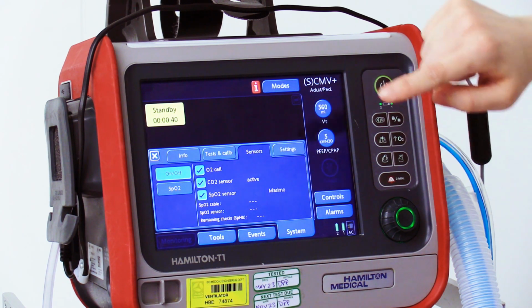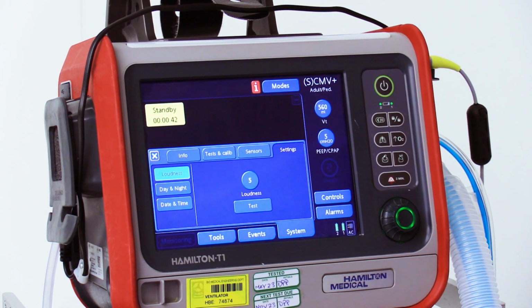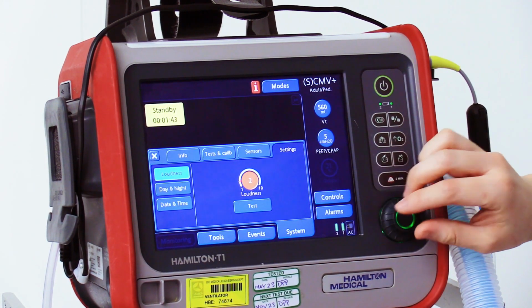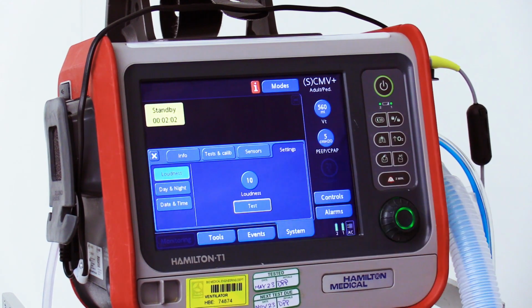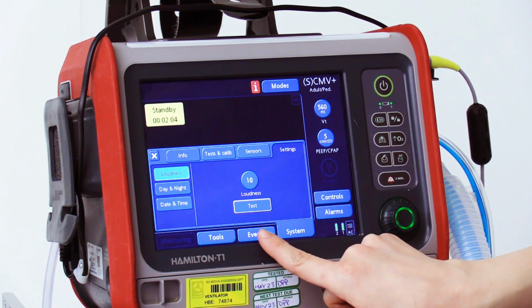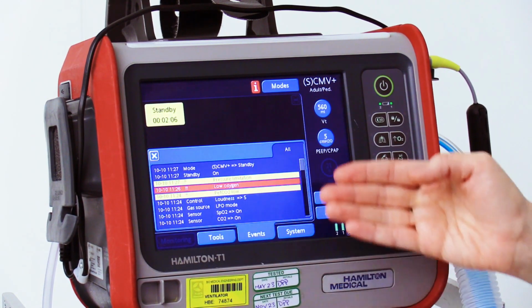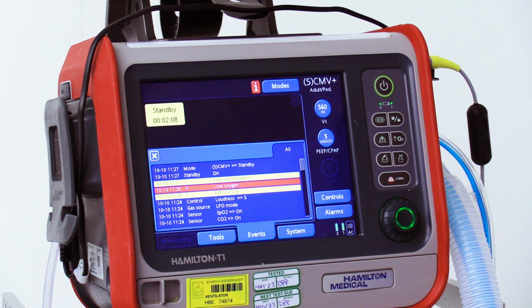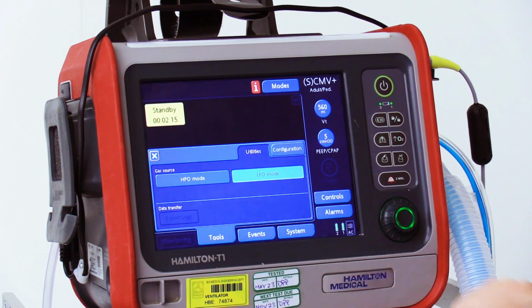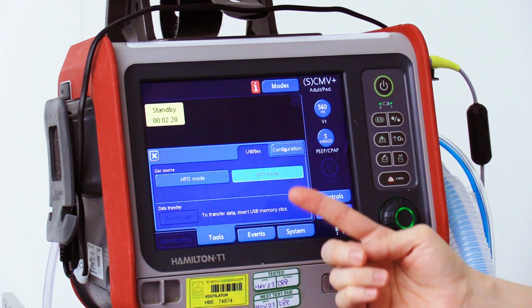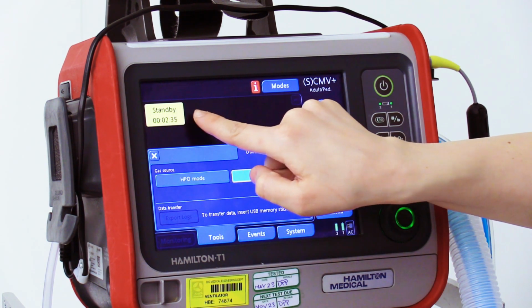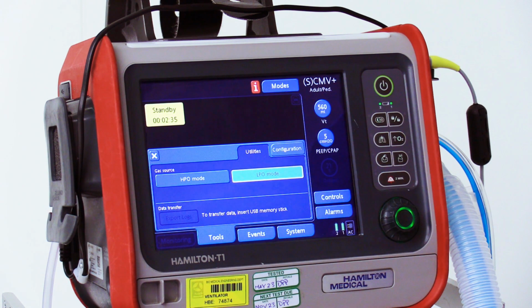the CO2 sensors. Then next you'll find the Settings tab where you find the loudness adjustment from 1 to 10, with 10 being the loudest and 1 the quietest. Next tab is called Events, which is the logbook for the last 1,000 events, including setting changes and alarm messages. Next tab is the Tools tab where we can select between high-pressure oxygen and low-pressure oxygen. To change these settings, remember that the ventilator should be on standby mode.